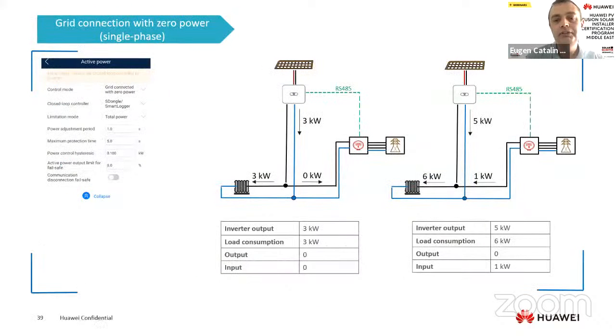This is grid connection with zero power. The inverter will follow the consumption. In this situation, it can cover the 3 kilowatts consumption and will work in limitation at 3 kilowatts. Here, the inverter cannot cover the load, so it will work at maximum power, and the rest will be taken from the grid. It's simple. Important here is this meter, to measure the total consumption and to measure correctly.